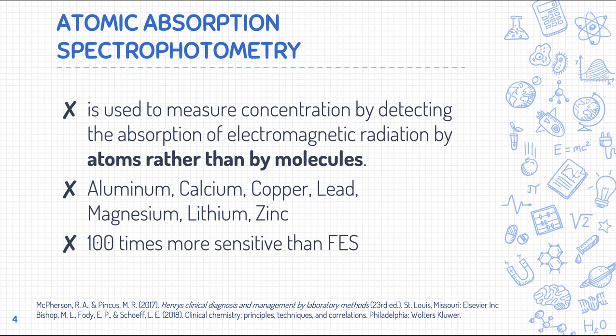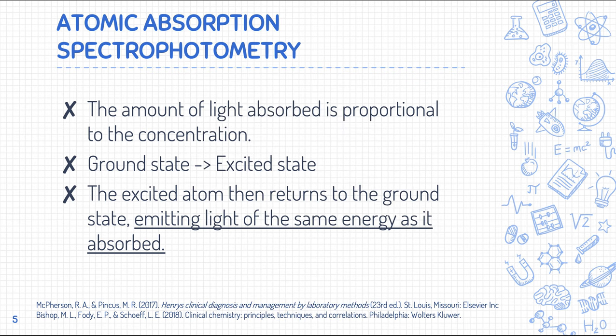AAS is 100 times more sensitive than FES — flame emission spectrometry. FES is a very insensitive and non-specific method, which is why we use AAS more than FES. When it comes to determining concentration using AAS, the amount of light absorbed is directly proportional to the concentration of your analyte — very much similar to spectrophotometry.